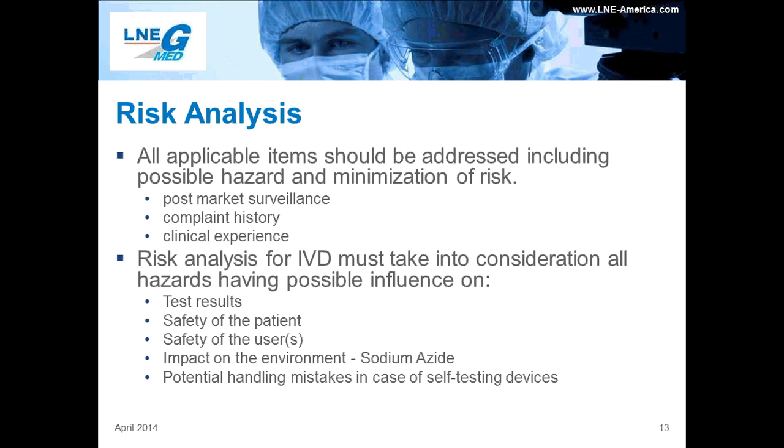Your risk analysis should address items including possible hazards and minimization of risk. Risk analysis should include any post-market surveillance experience, risks derived from complaint history, and risks from clinical experience. When performing risk analysis for diagnostics products, you must take into consideration all hazards which may influence test results, the safety of the patient, the safety of the end user, and any impact on the environment when disposing of the device. So, for example, disposal of products containing sodium azide in the EU requires special consideration. Risk analysis also should address any potential handling mistakes in case of self-test devices.